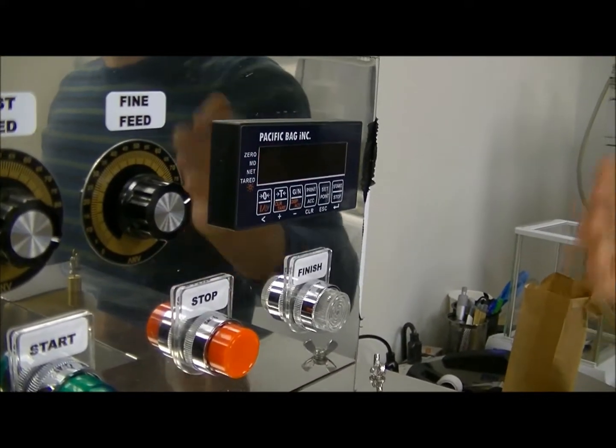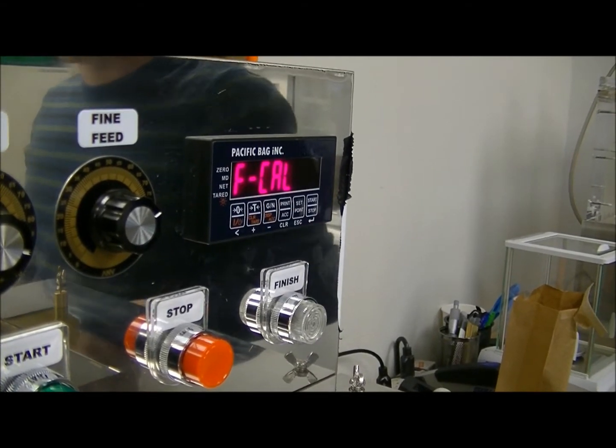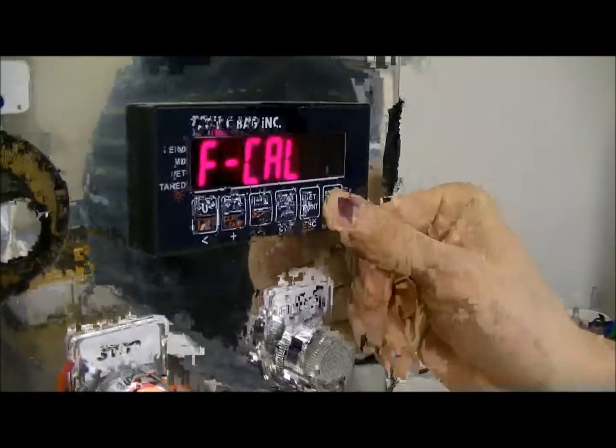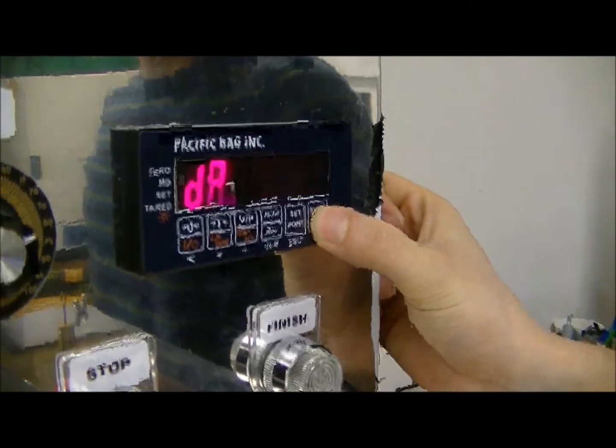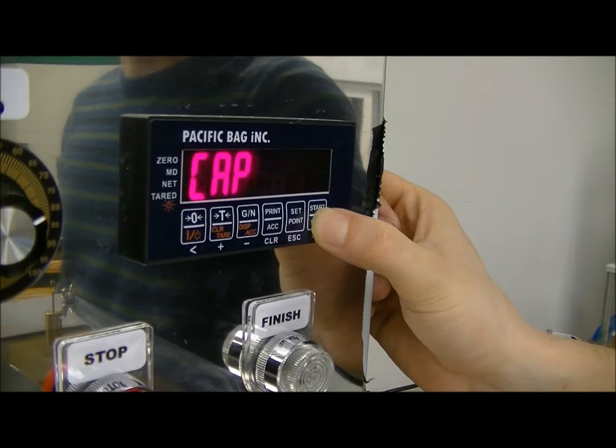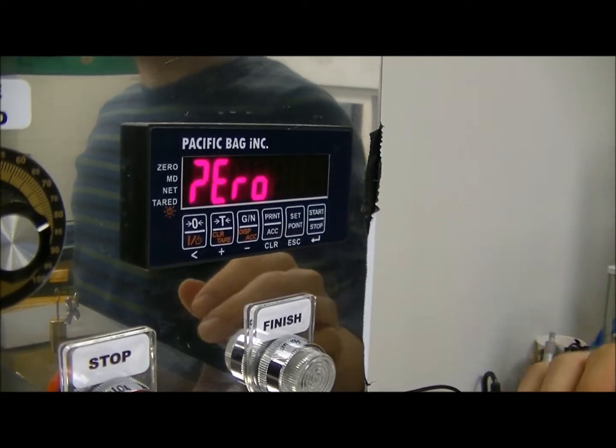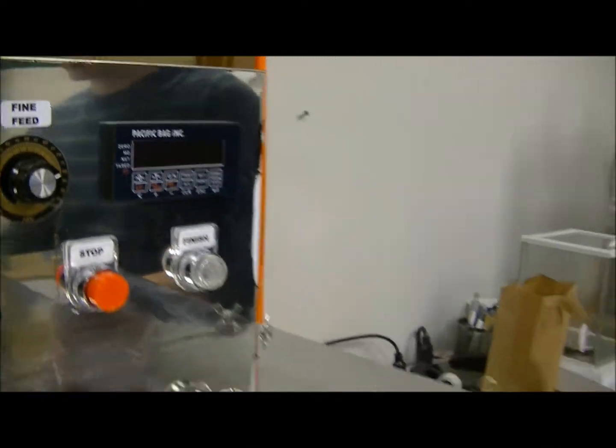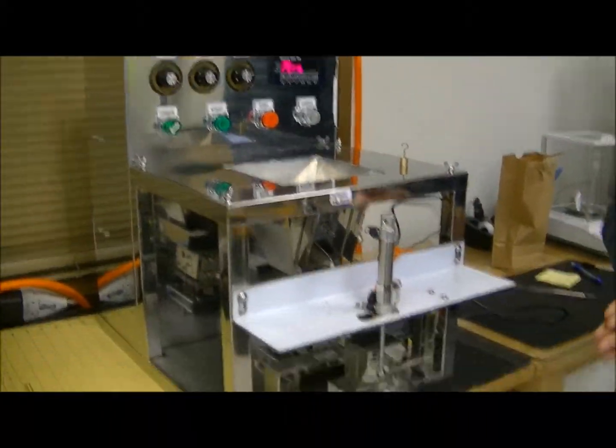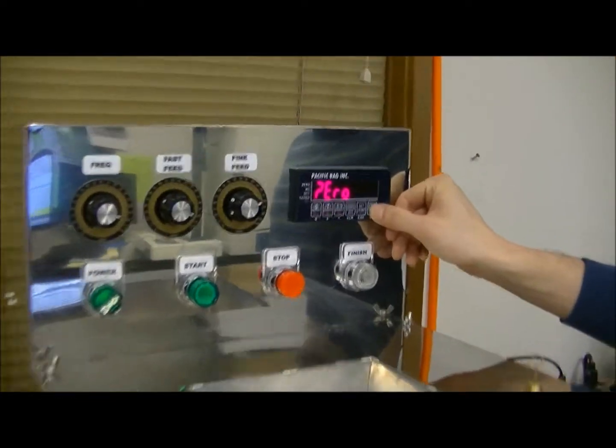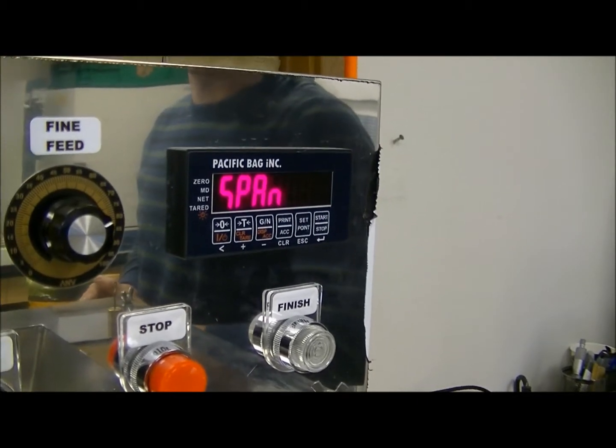As soon as we turn it on, we'll see it'll go straight into calibration mode, and the machine will be blinking FCal. Now, what we're going to do is hit the return button through the settings. These are adjustable, but are factory preset to be the settings that we need for our calibration here. We're going to hit return until the machine starts blinking 0. Next, we're going to make sure that the hopper and the weigh bucket are completely empty and that there's no additional weight on there. This is going to determine the 0 weight of the load cell. So once we've made sure that there is no additional weight in the weighing bucket, go ahead and press this return button and the machine will 0 itself.